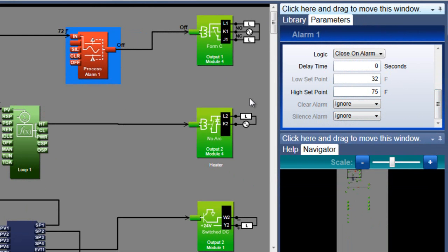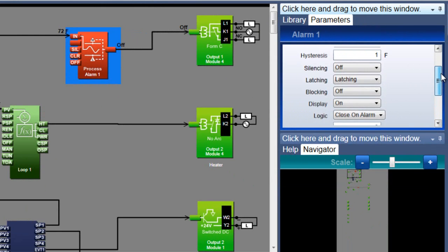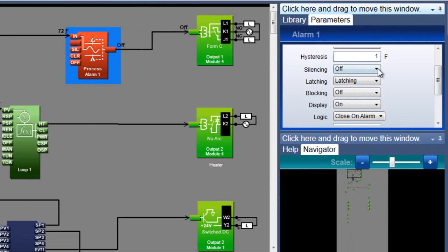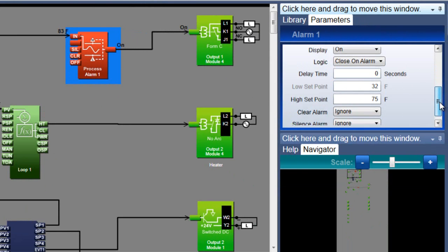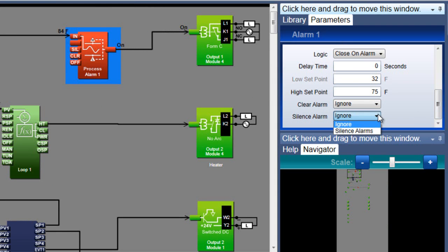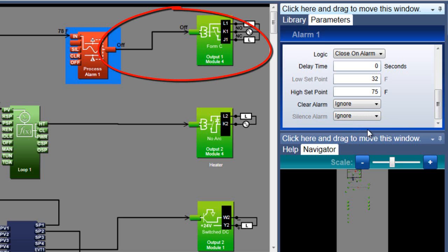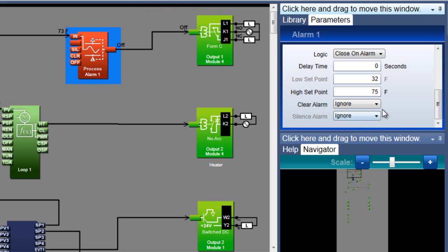To be able to turn the alarm transmitter off before the temperature drops back down, I'll turn on the silencing feature. Now when the alarm occurs, I can silence it even when the temperature is still above the high setpoint. This doesn't clear the alarm state, so it doesn't clear the alarm message from the controller display, but it does turn off the transmitter and the output connected to it. Once the temperature does drop below the alarm setpoint, I can clear the alarm.